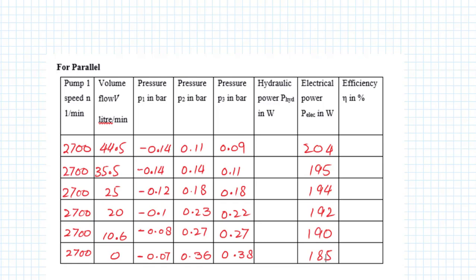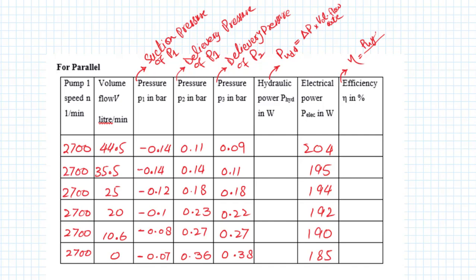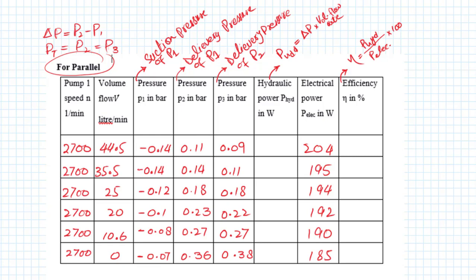In this reading, where P1 is written, that is suction pressure of pump 1, and P2 is delivery pressure of pump 1, and P3 is delivery pressure of pump 2. Hydraulic power formula is delta P into volume flow rate, and efficiency formula is hydraulic power divided by electrical power. Delta P will be calculated from P2 minus P1, and total pressure will be equal to P2 and P3.